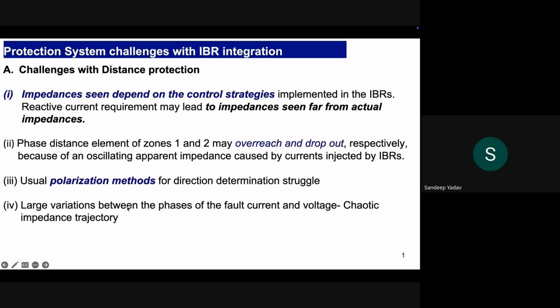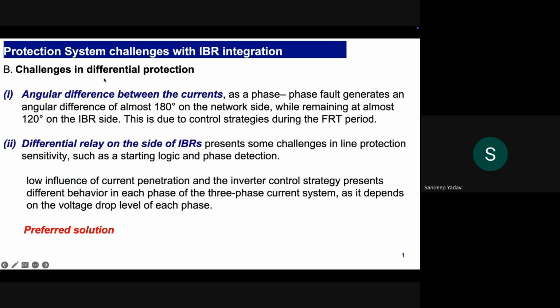And the last point is that there is a large variation between the different phases of the fault current when it comes to IBR fault injection. So if the distance relays are finding it difficult to detect the fault, the usual go-to protection is differential protection, and by far differential protection works just fine even in the case of fault currents as seen from the inverter-based resource. However, there are minor nuances which need to be looked into.